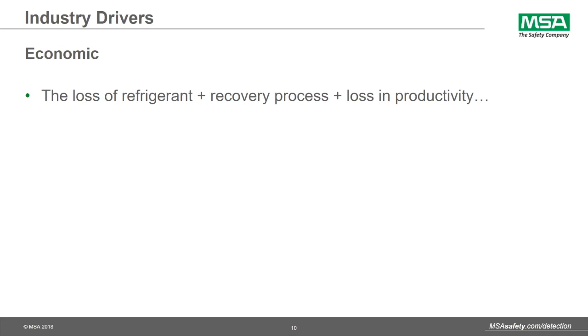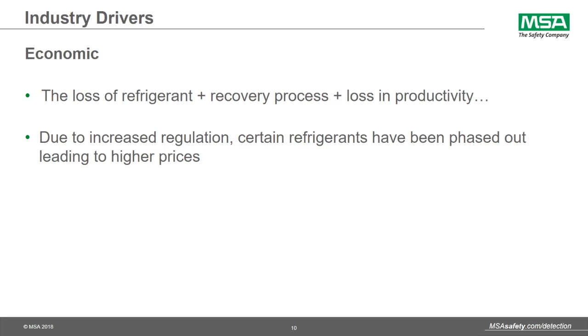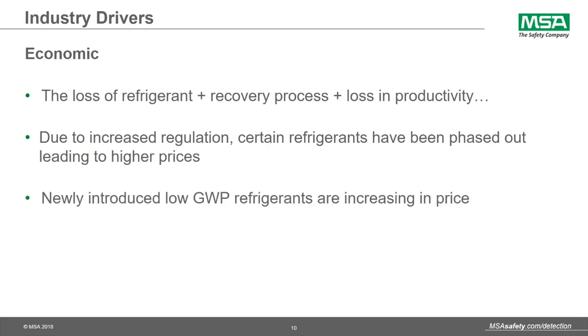The second industry driver is economic. The overall theme is reducing operating costs. When you combine the loss of refrigerant plus the recovery process, and then the safety factor with evacuation and safety procedures, it equates to loss in productivity, and that can really add up. The other point is around scarce supply of high GWP refrigerants that are becoming harder to locate. And of course, the newly introduced low GWP refrigerants are higher priced until they've really penetrated the market and are easier to procure.